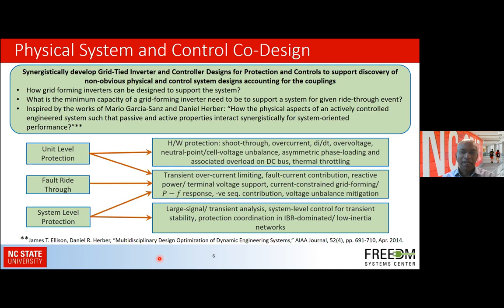When you look at the system side, we have to evaluate and understand the system through large signal and transient analysis, system level control for transient protection, stability, and then the protection coordination in an IBR dominated network. And the coupling, one aspect of the coupling is through this fault ride-through. So there could be others, of course, but in relation to this talk, the fault ride-through aspects would be the transient overcurrent limiting of the hardware, the fault current contribution that would support the system, reactive power support, the P-f response, negative sequence contribution. So those would be the elements of the fault ride-through controls that couple the unit with the system.